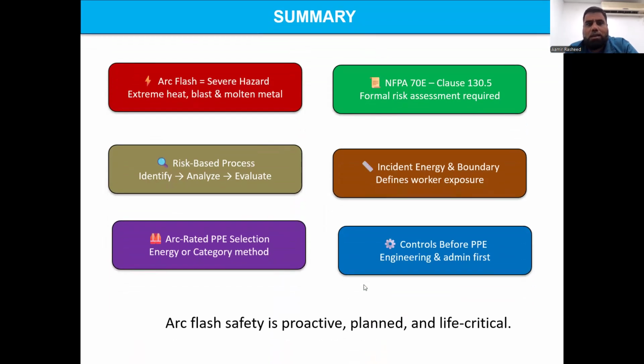So that's all, gentlemen, and we are going to have a summary of this session, where we discussed arc flash. What is arc flash? It is basically a severe electrical hazard which is capable of causing fatal burns, blast injuries, and equipment damage. NFPA 70E clause 130.5 requires a formal risk assessment before performing any kind of activity on any energized electrical equipment. So the risk-based approach is to identify, analyze, and evaluate. You need to understand what incident energy and boundary define.